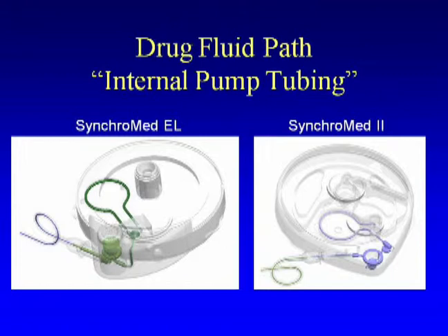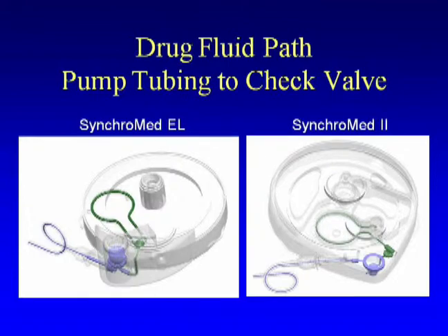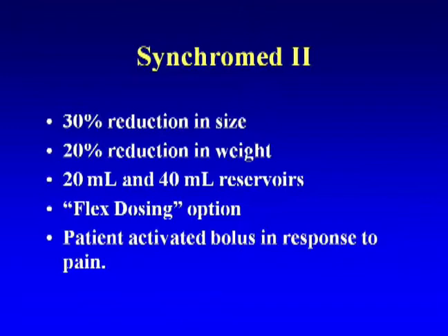A check valve was added in the new pump: when you access the side port and inject, a one-way valve prevents the solution from going backwards into the reservoir. The older model did not have this check valve. The SynchroMed II is about a third smaller and about a fifth lighter than the EL. The reservoir volume increased from 18 mL to 20 mL, with a new option of a 40 mL pump. Flex dosing replaced complex continuous, and patients can now give themselves a patient-controlled bolus during the day.